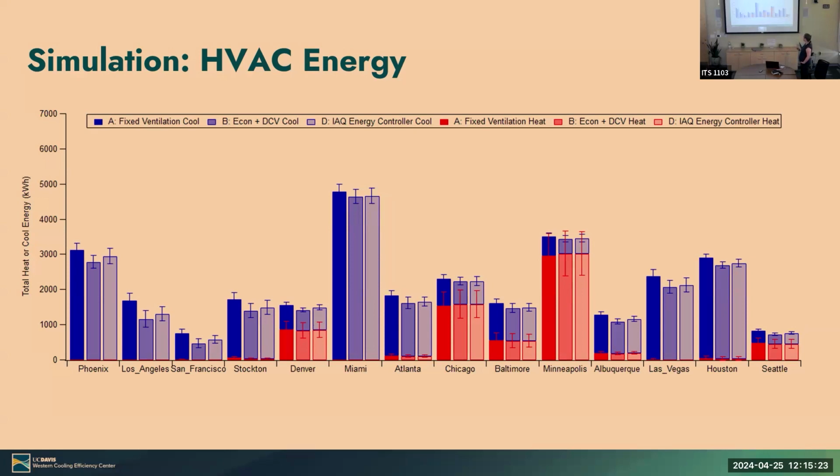So you can see here the energy impacts are small, but there's a few hundred kilowatt hours to be had. And what's important to remember, I'm only proposing a control change, right? So it's not like you've got to go put in a whole new HVAC system or something to get a couple hundred kilowatt hours of savings. Essentially, it's a back end programming change.